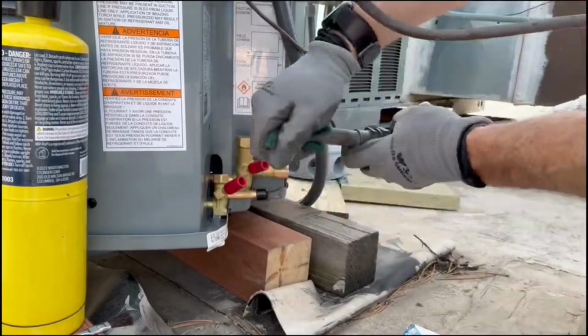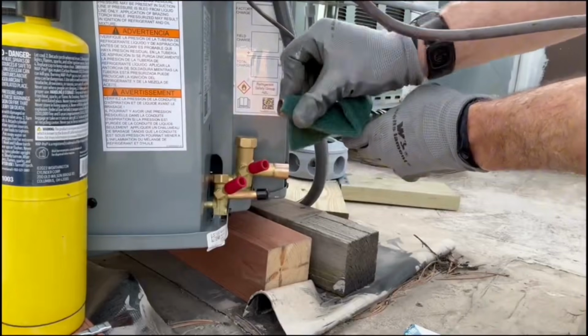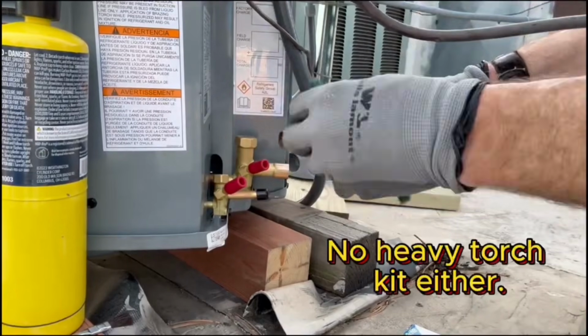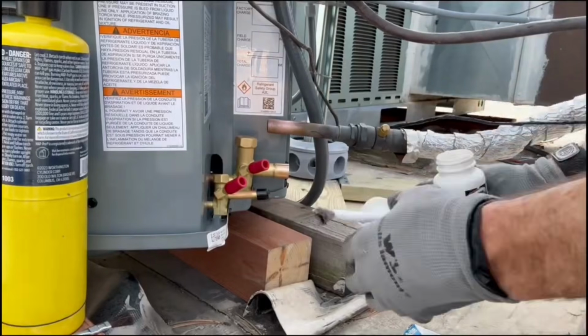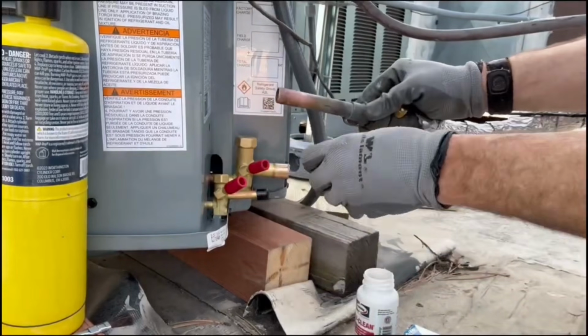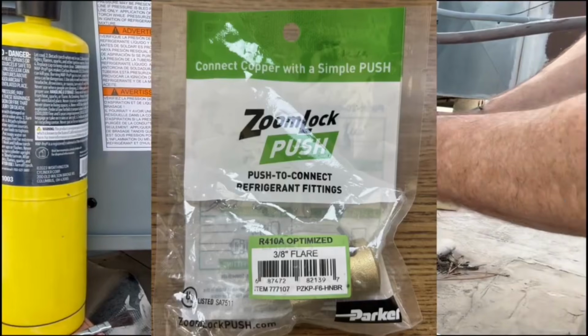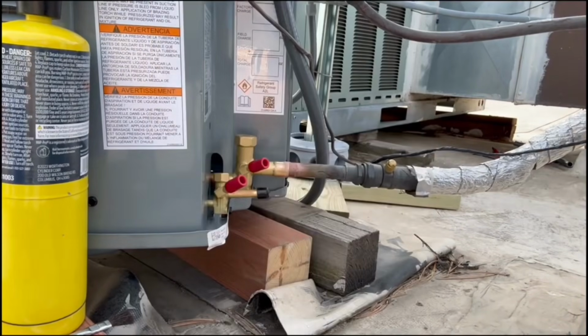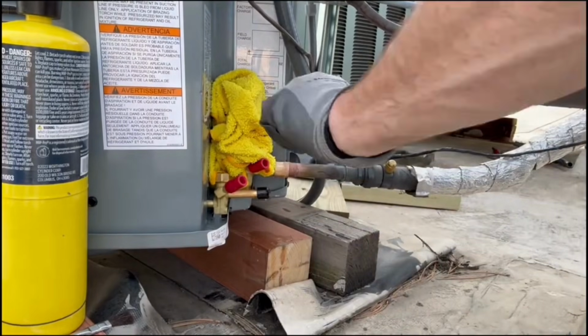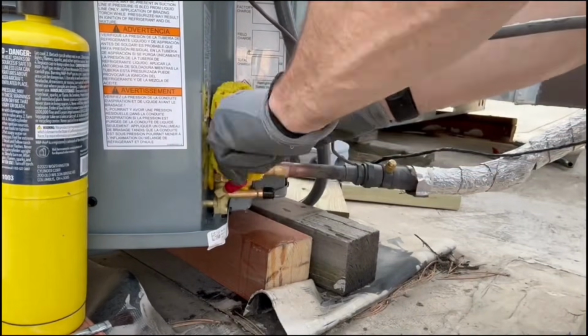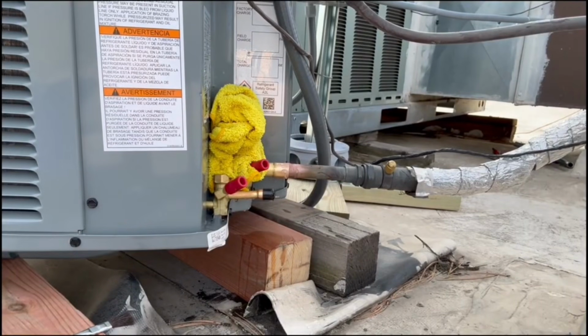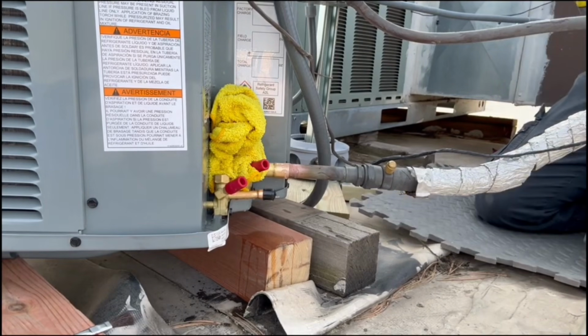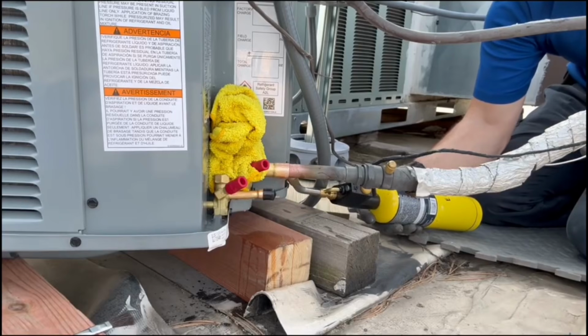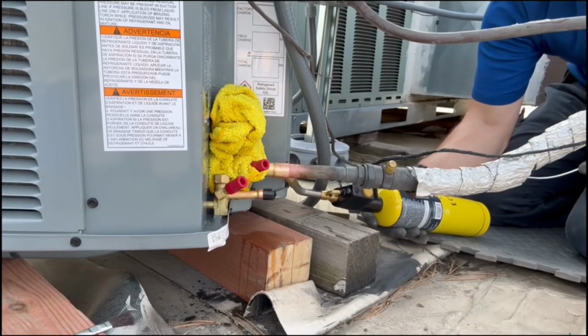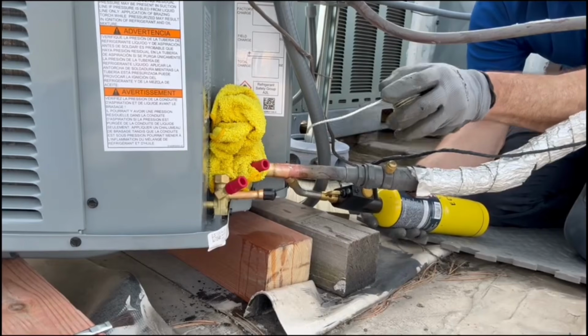But this stuff works great. Don't have to get it as hot as if you were going to be brazing. It's nice. Or you might be able to use those push to connect HVAC rated fittings. That's another option. Then you want to keep your valves cool, whether you're brazing or soldering with Stay Bright 8. You want to put a nice cold wet rag around your service valves because you don't want to overheat those, obviously. And try to keep your flame away from the service valves. That's the other nice thing about using Stay Bright 8 and a MAP gas torch here. You can see it hardly takes any time at all.